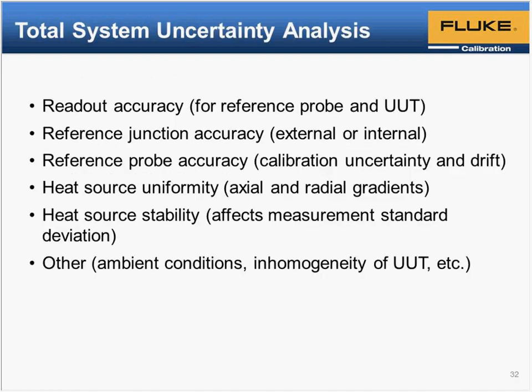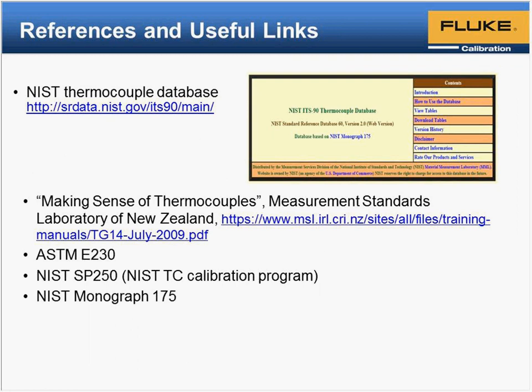for the presentation, the last slide here has a link to the NIST Thermocouple database, which is very, very handy. This is what the ASTM thermocouple tables are based on, and NIST has a nice little tool here that helps you with the letter type and the temperature range you are working with. We'll have a link to the New Zealand NMI, and they have some interesting documents about thermocouples, and we also list some other references that are typical for thermocouple calibration, like ASTM and NIST SP250 and NIST Monograph 175. So I'm going to run over time.